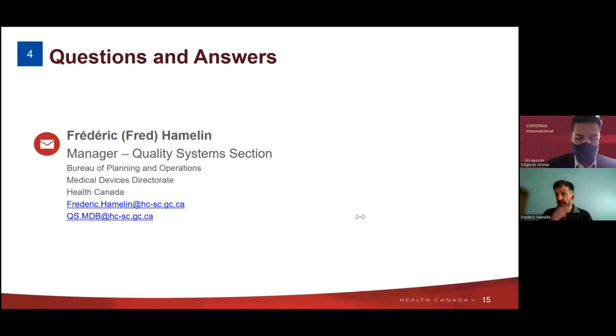And when I say grade 4 or 5, we have rules for grading nonconformities. So they either start out as a 1 or a 3, depending on whether it has direct impact on the product or not. And then to this, we add escalation factors like, is this something that's recurring? Has this happened before in the last few years? Does this lead to the release of non-conforming product? Things like that. So using those rules, we set a score of 1, 2, 3, 4, or 5.